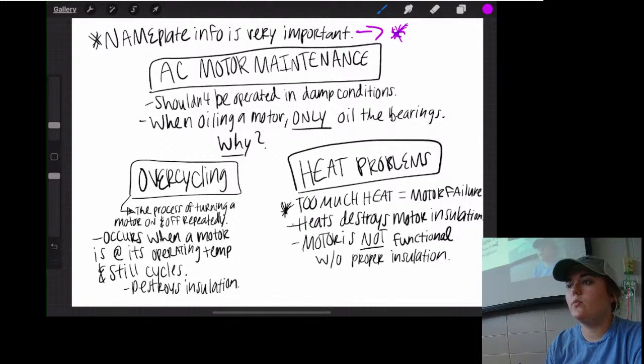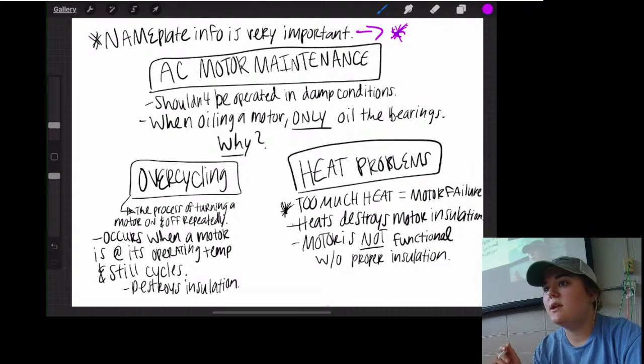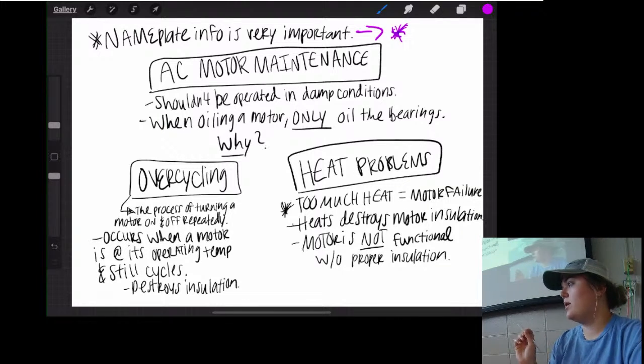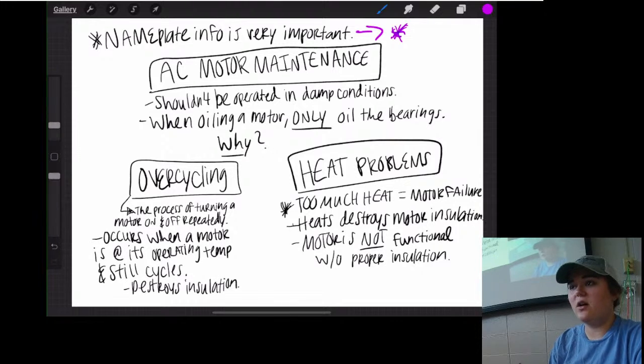So why would that be? Because it's electrical, not everything will work with it, and some oil is conductive. Well, they do make some oil that's non-conductive, but it will bring down how fast it can spin, and if you over-lubricate something, it's going to make wear and tear worse on that motor because it won't be operating at full capacity. Also think about if you get oil in a corner somewhere, it attracts dust, and dust is not good for a motor — you don't need dust in your motor. So that's why you never want to over-oil a motor when doing preventative maintenance.